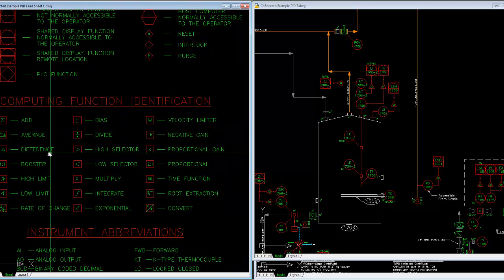Hey, these two devices that are measuring the same thing on a very critical stream are in disagreement with each other, and they're off by some threshold value that may provide an alarm, or the system may take action to a safe state based on what is the safest action to take when two devices are not in agreement, based on the nuances of the process. For example, if a tank is filling up and one meter is saying it's 50%, the other meter is saying it's 98%, you may want to take the action to stop filling the tank, even though you're not sure which one's right, because the greater harm would be to overflow the vessel, potentially. Or maybe not. But anyway, that's an example where a difference may be used.